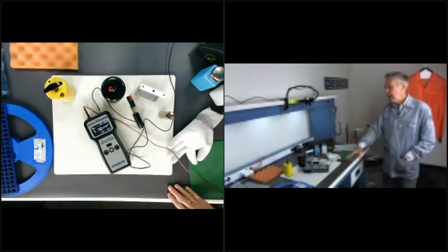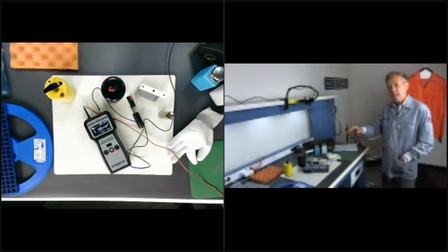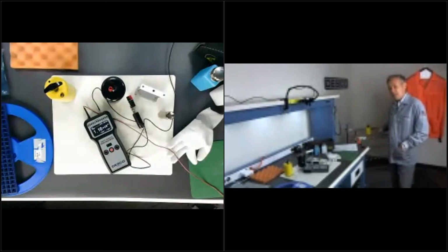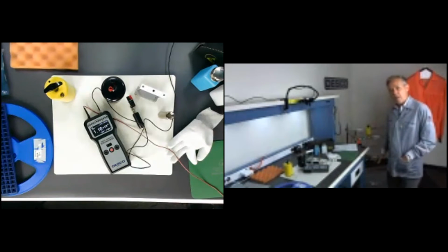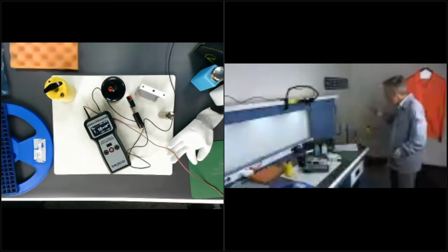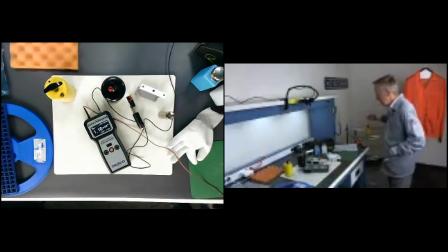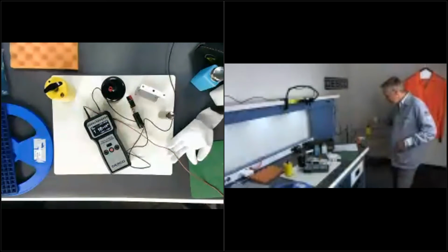As I mentioned, if I find that was out of spec, now I'm going to work backwards. I'm going to go check the RTT of the surface. I'm going to check the resistance to ground or the RTG of the floor, because I want to find out which is the weak link. Maybe I got a bad ground, maybe my floor is out of spec, whatever. But the mandatory requirement to start with is RTG. So should we do floor next, Steve?